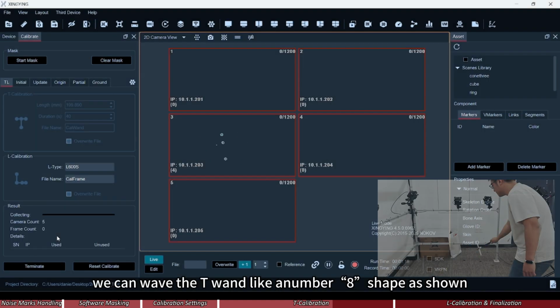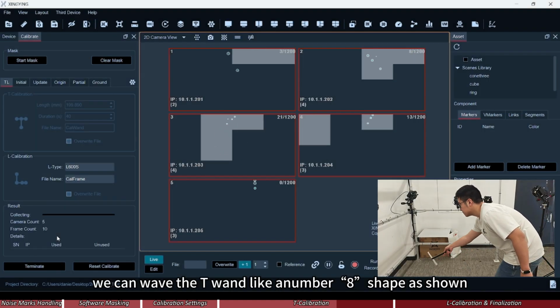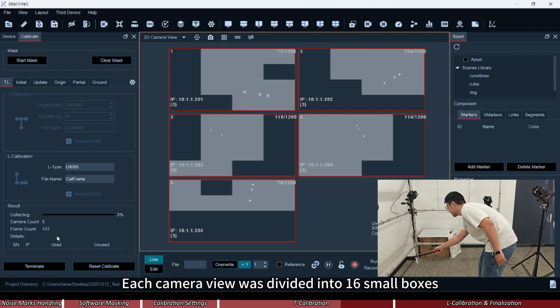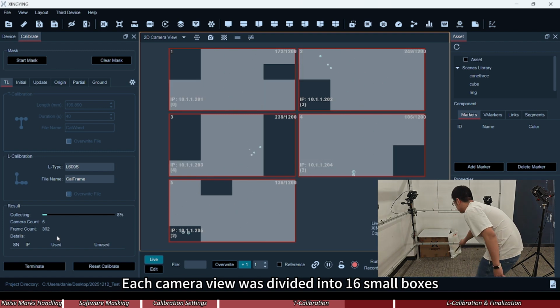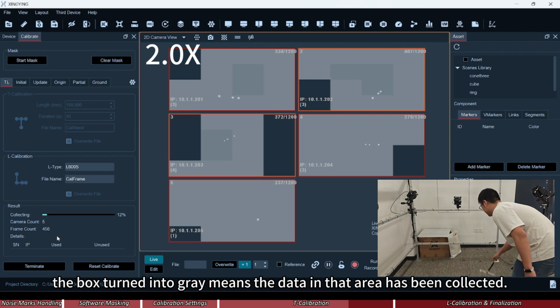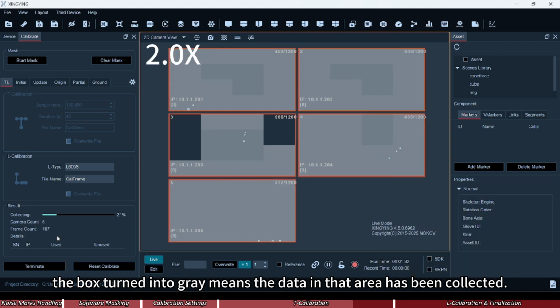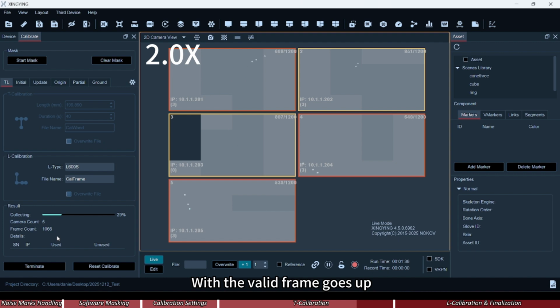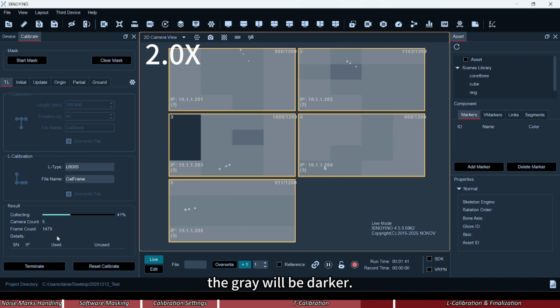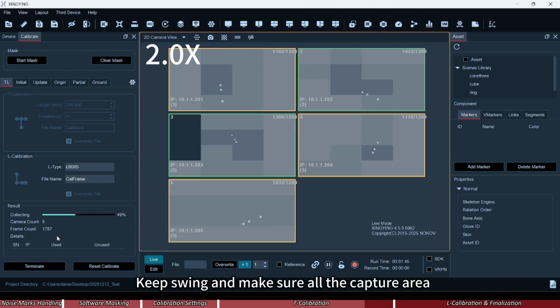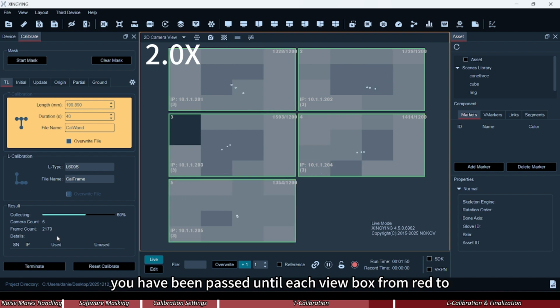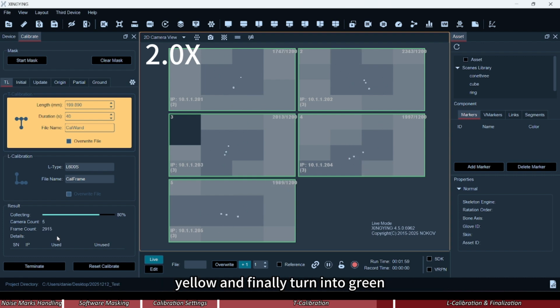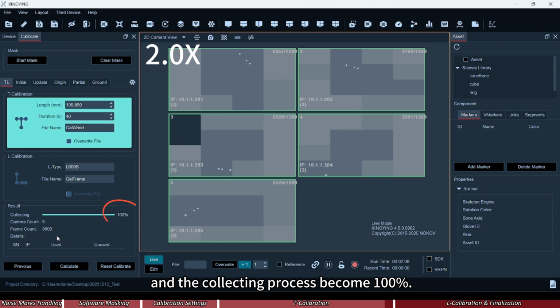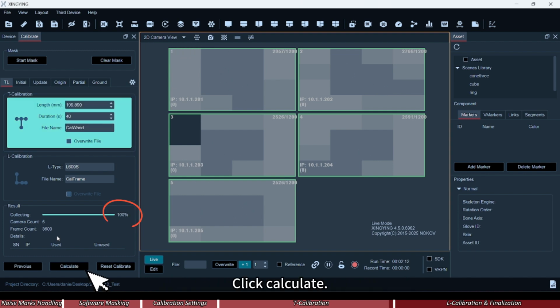We can wave the T wand in a number 8 shape as shown. Each camera view is divided into 16 small boxes. A box turning gray means the data in that area has been collected. As the valid frames go up, the gray gets darker. Keep swinging and make sure you pass through all of the capture area until each view box turns from red to yellow and finally green, and the collecting process becomes 100%. Click calculate.